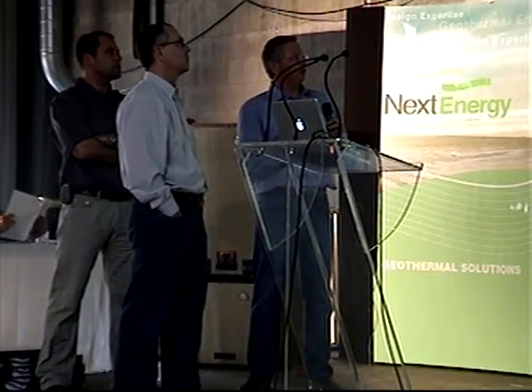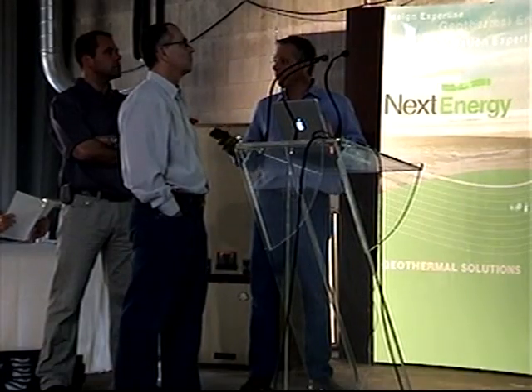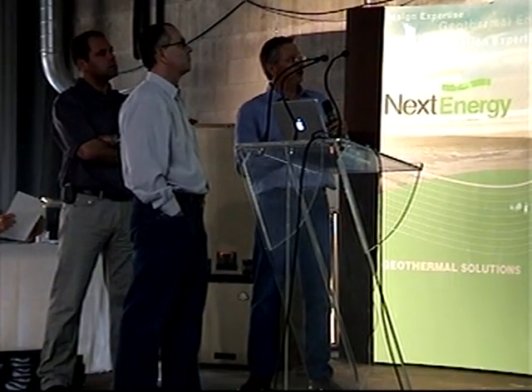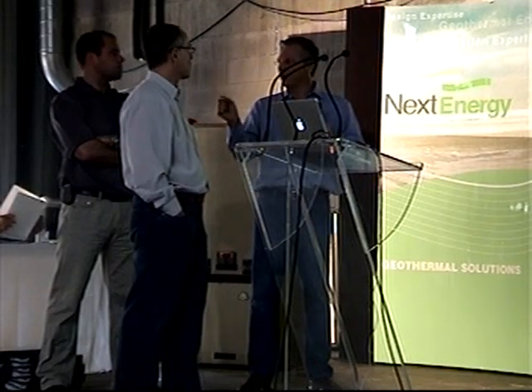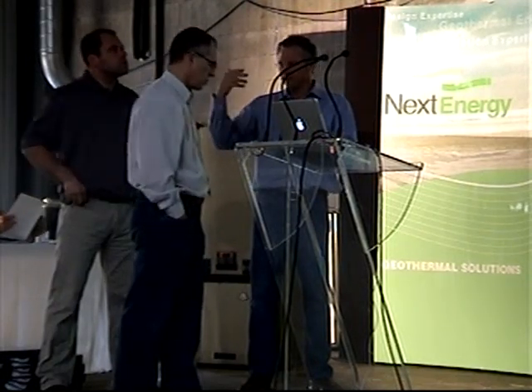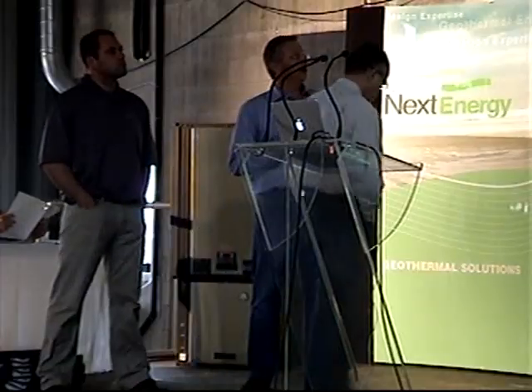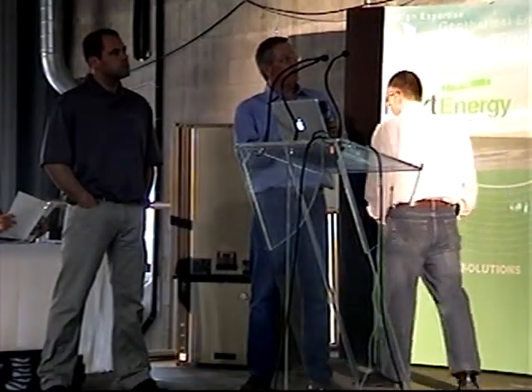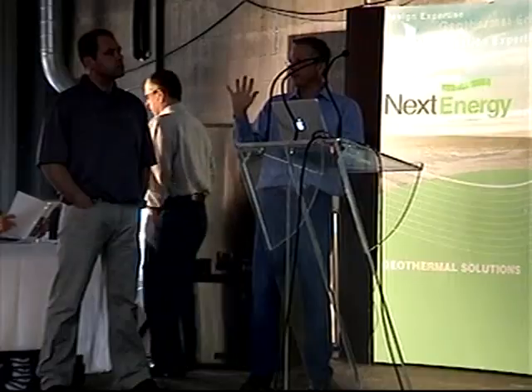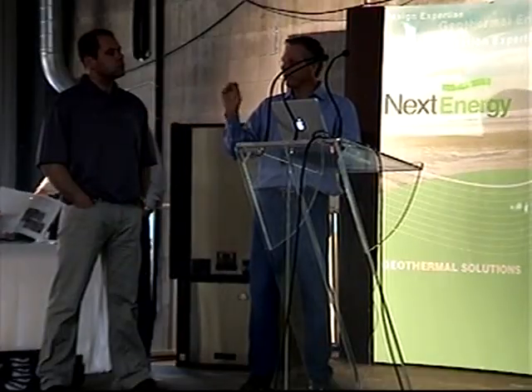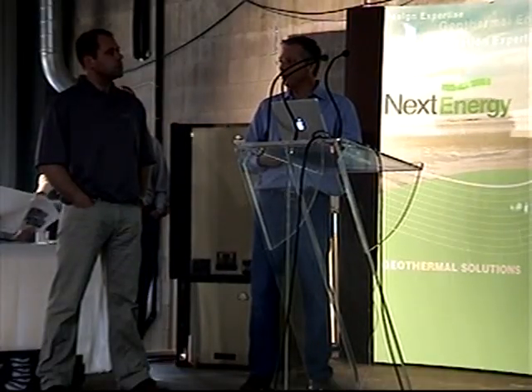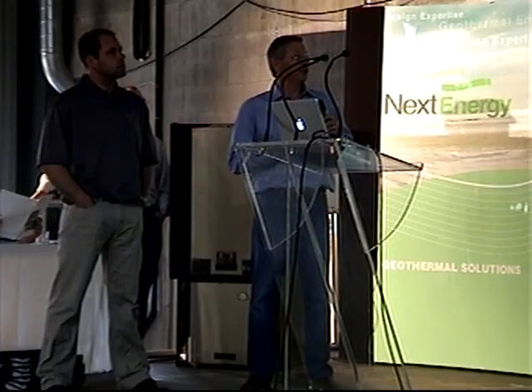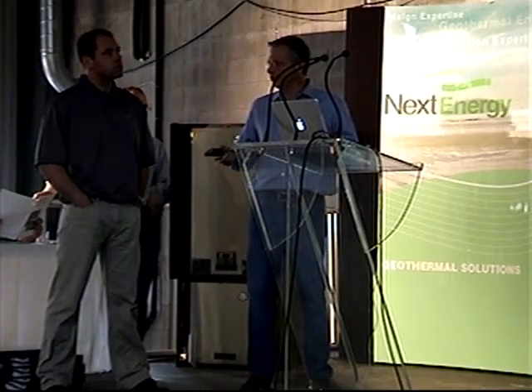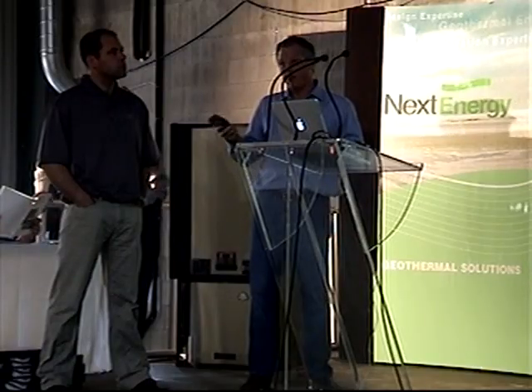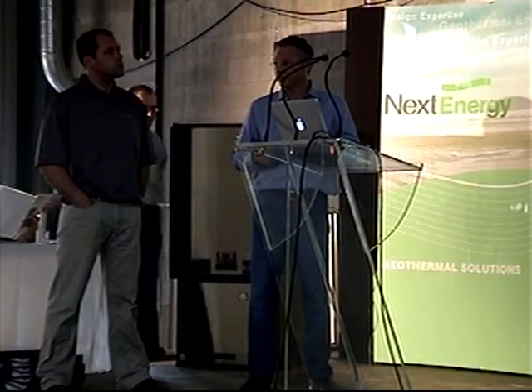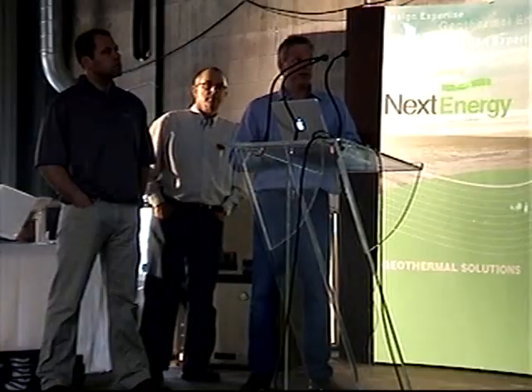If it's got a UPS warning, which means what I told you, that we think the unit's operating abnormally, you go to the board, that light is still on green because the unit is still going to run. Everything's acting fine, but there will be a 5-second fault light and then 25 seconds off. So they'll just see this random kind of hit on their fault LED. They'd wonder what it is. It just means that your unit might need service. It's kind of like a service reminder. You know, most common cause of this is a dirty air filter, which would raise the condensing temperature.